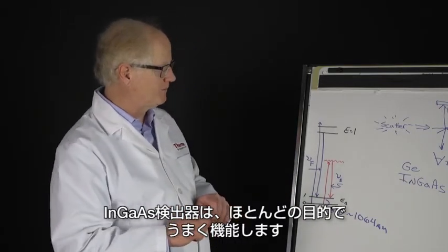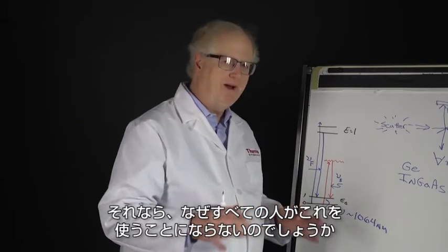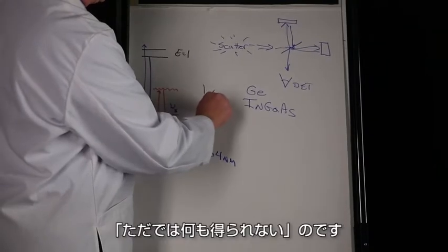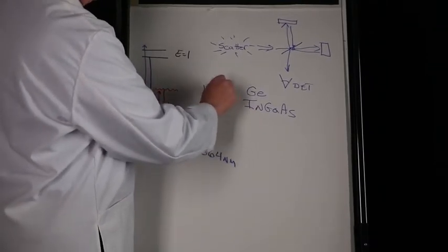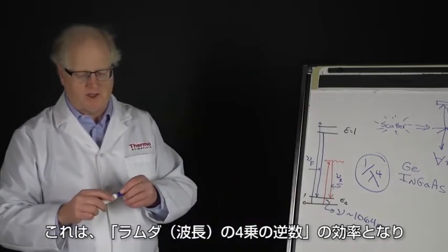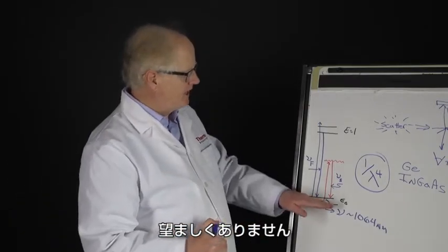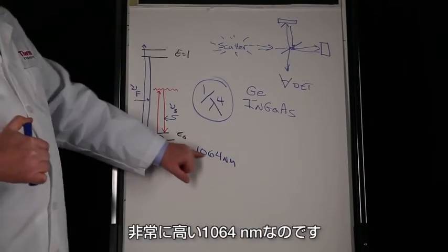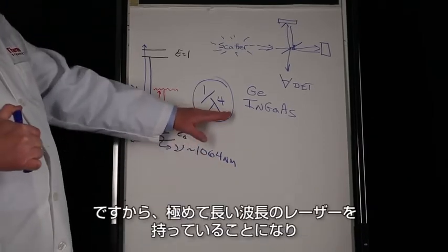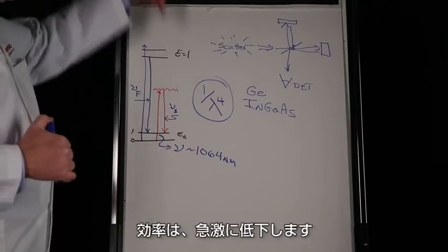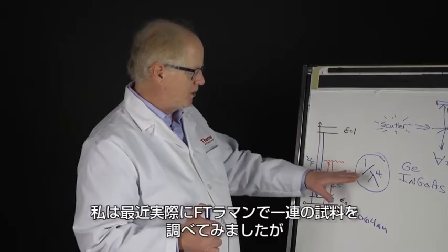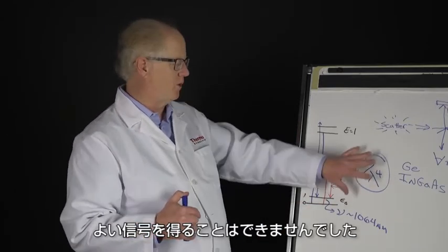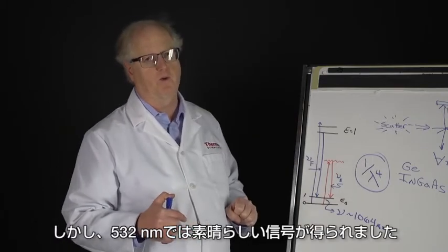So why doesn't everybody do this? It comes back to that big problem: you don't get something for nothing. It's the one over lambda to the fourth efficiency. Yes, you're avoiding fluorescence, but at one over lambda to the fourth where lambda is now way up here at 1064 nanometers. The efficiency drops in a hurry. I've actually had recently a set of samples that we were unable to get good signals for on the FT Raman but got great signals at 532.